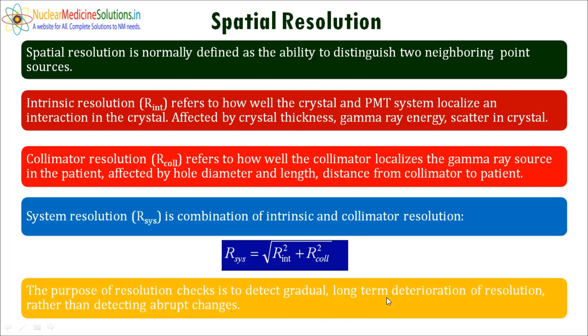So the purpose of the resolution test is to check or detect the gradual long-term deterioration of resolution rather than detecting abrupt changes. We can see this example where two point sources are at a distance which is equal to the resolution of your gamma camera. Suppose it is 12 mm. So if these two point sources are at 12 mm or more than 12 mm, then we can distinguish or separate them as two point sources, right?